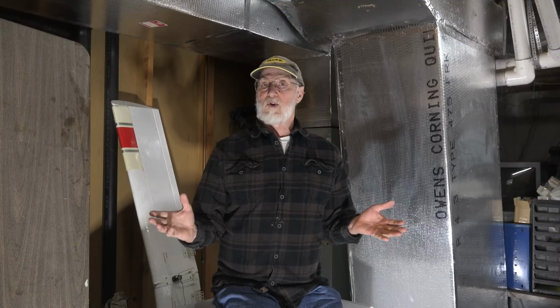There are a few things, however, that I did not go over and that you can't read with a manometer on ductwork. Because if you watch these videos, you've noticed that virtually everything is done with a manometer. When I talk to you about total static pressure, that was always external of the air handler. There is static pressure drop inside the air handler. The heat exchanger, if it's a gas or oil furnace, there's a certain pressure drop across that heat exchanger.